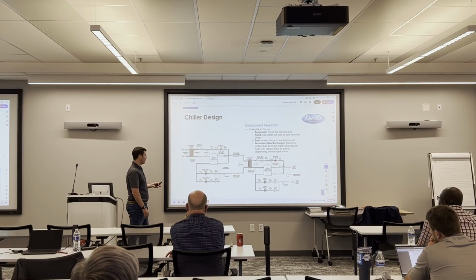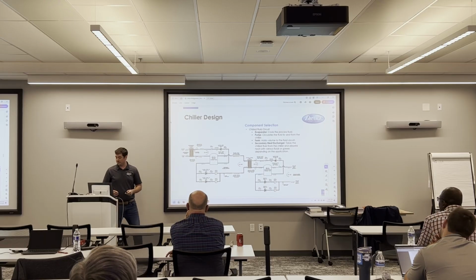So a couple of things to note here. We got some redundancy built into this type of system. So we have redundant glycol process pumps, and we got redundant water pumps. Only one of these pumps will ever run at a time. If we have any sort of failure and our flow switch stops detecting flow, it'll shut this pump off, kick this pump on, and the customer isn't any the wiser.